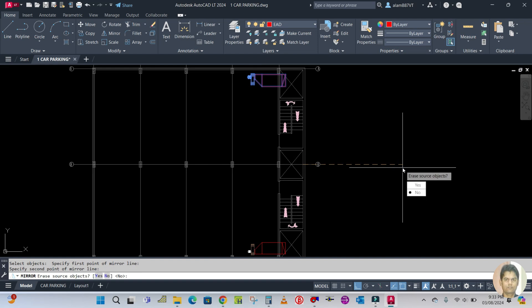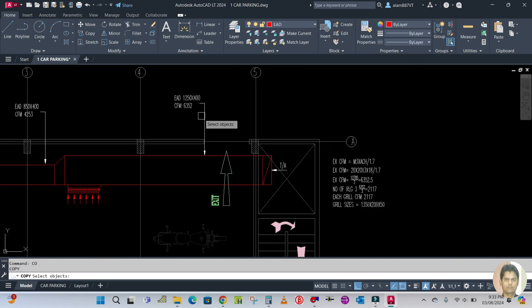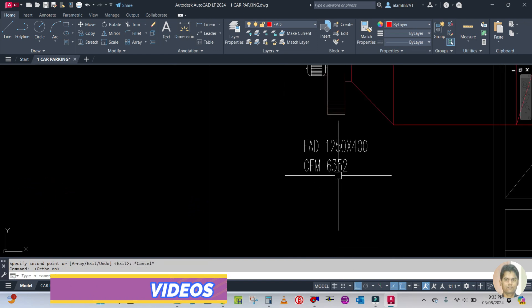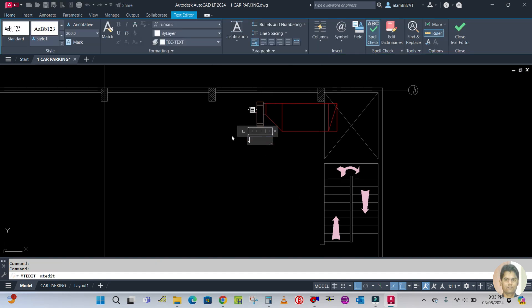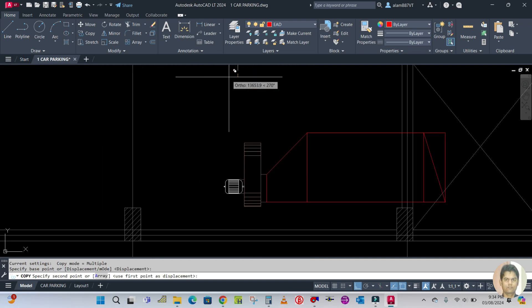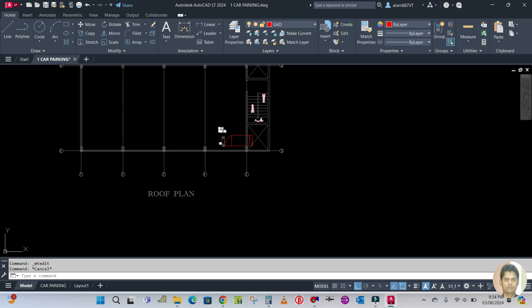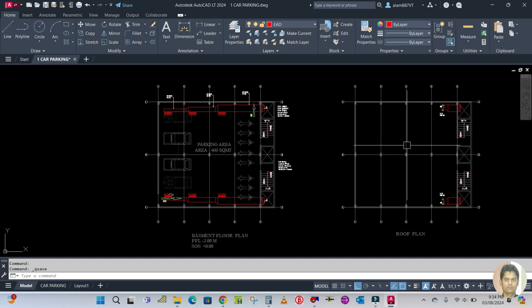Erase source object — I don't want to erase, so type N, enter. So this is exhaust fan one. Copy the text from here and place it here — EXF01 at 6352 CFM. Similarly copy this for exhaust fan 2 — EXF02, same CFM. The exhaust fan design is over. The exhaust duct and fan design is complete. Next is the fresh air fans — we have to design the fresh air duct in the next video.